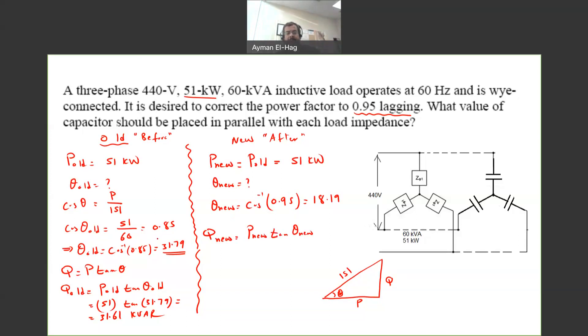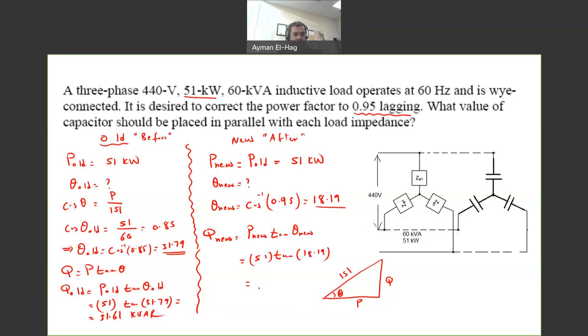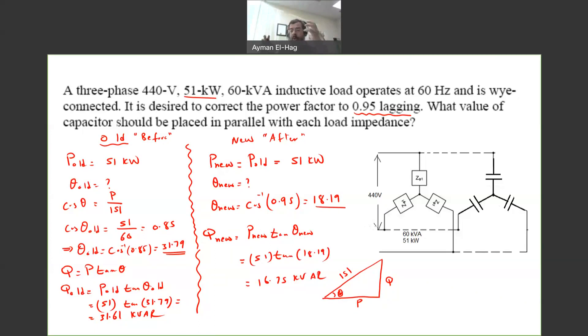Now we find Q_new = P_new × tan(theta_new) = 51 × tan(18.19°) = 16.75 kVAR. What happened here: the load alone was consuming 31.61 kVAR, but the combined load and capacitor bank now consume only 16.75 kVAR. This means the capacitor bank is actually supplying reactive power — it is consuming negative reactive power.